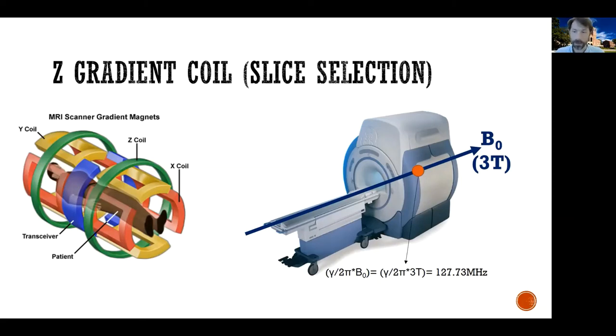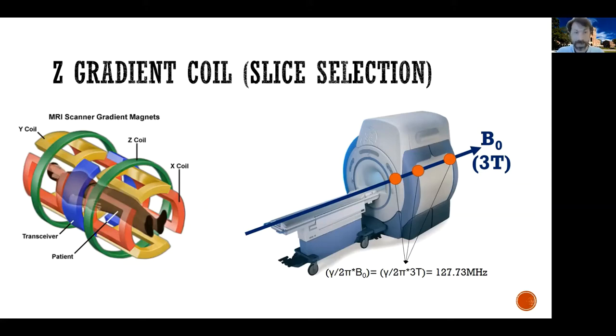At three Tesla, a proton would be spinning at 127.73 megahertz. A proton at any other location would also be resonating at 127.73 megahertz — all these protons are resonating at the same frequency. So if I inject a radio frequency pulse at 127.73, I would be exciting all of these protons. What I want is a way to only excite the protons at one specific level — here, or here, or here. To do that, we use a Z gradient coil.